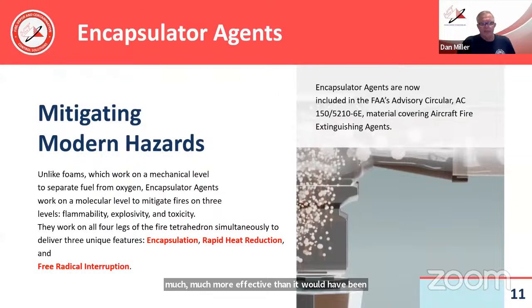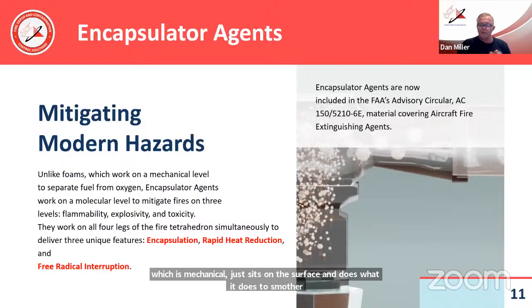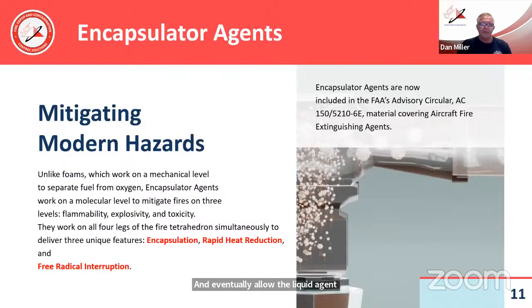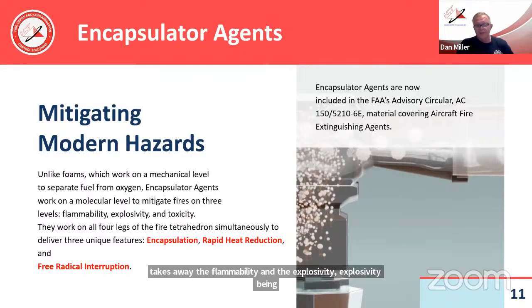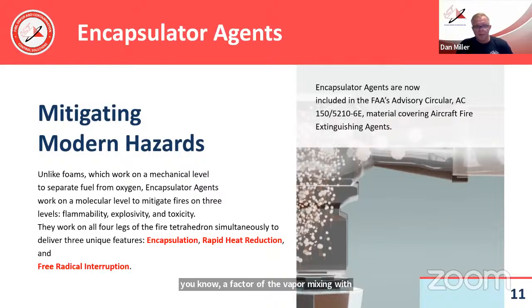It helps mitigate modern hazards. Unlike a foam, which is mechanical and just sits on the surface to smother and eventually let the liquid agent underneath cool, the encapsulator works on a molecular level—it mixes with the fuel. It mitigates the fire on three levels: taking away the flammability and the explosivity, which is a factor of vapor mixing with oxygen in the atmosphere immediately above the fuel.